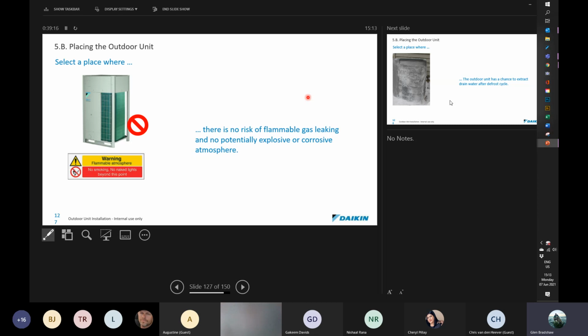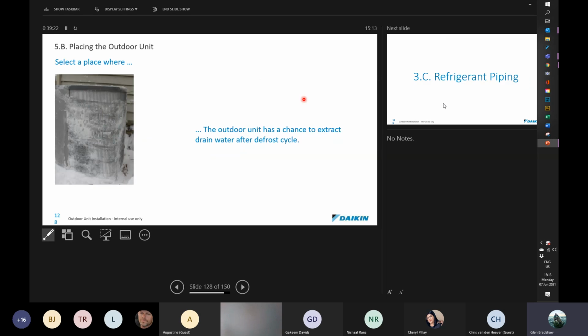We've also spoken about there being no risk of flammable gas leaking and no potentially explosive or corrosive environment. And that's what we've been discussing. Select a place as well where the unit has a chance to extract drain water. That's just a bad translation. Basically, to discharge any drain water during the defrost cycle, and also make provision for removing the defrost water. Don't allow it just to flow out the bottom of a unit onto somebody's paving or into an area where people might be walking. That ground will eventually get algae and become slippery, which becomes an occupational safety problem. So just keep that in mind with defrosting, that you provide access for the water to move away from the unit.